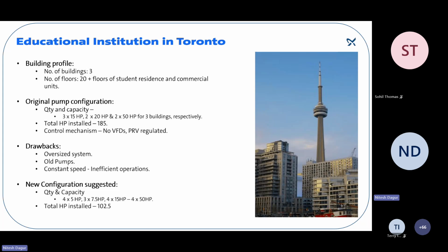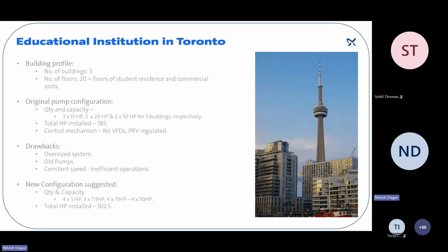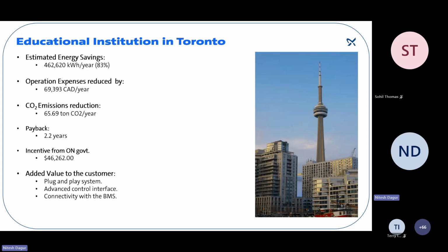So the total horsepower was reduced from 185 horsepower to 102.5. This is the kind of reduction that was possible, and we did it for the customer, and the buildings have been running fine ever since. There have been no complaints on water requirements. In addition to that, this is what the customer reaped from installing the newer solution. The estimated energy savings were close to 500,000 kilowatt-hours per year.